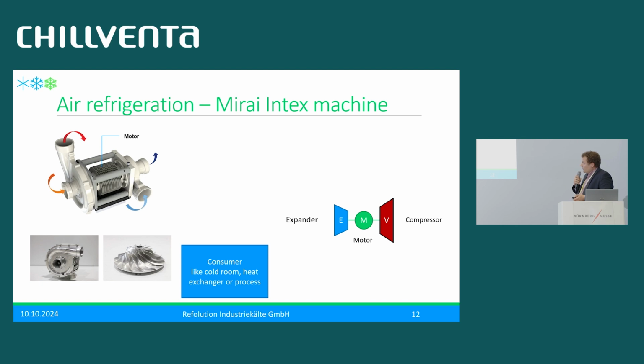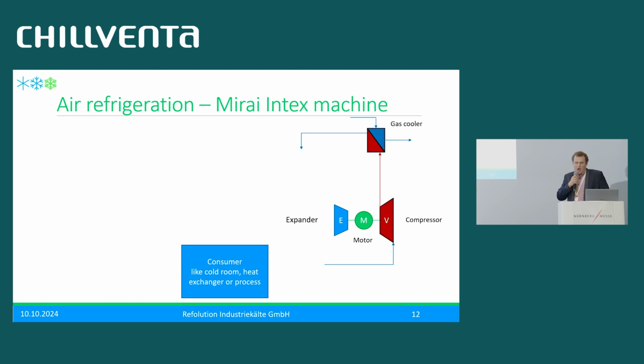So what we do is we have a storage room, say at -80. The machine is an open cycle, so you are already bathing in the refrigerant. Also a nice experience. Do this with ammonia or something else. So we suck the air from the room, compress it, and we have the high temperature, high pressure. Our high pressure on an open cycle machine is 1 bar overpressure. So also from a safety risk, this is a crazy machine. We cool it with cold water, 6 to 12 for example. Then we would have 20 degrees here, 1 bar overpressure.